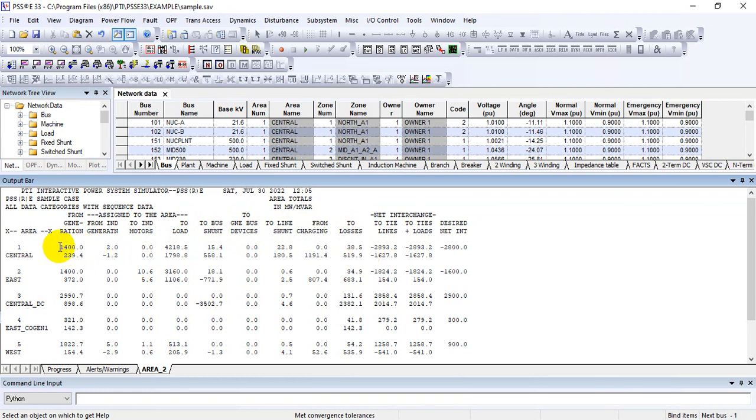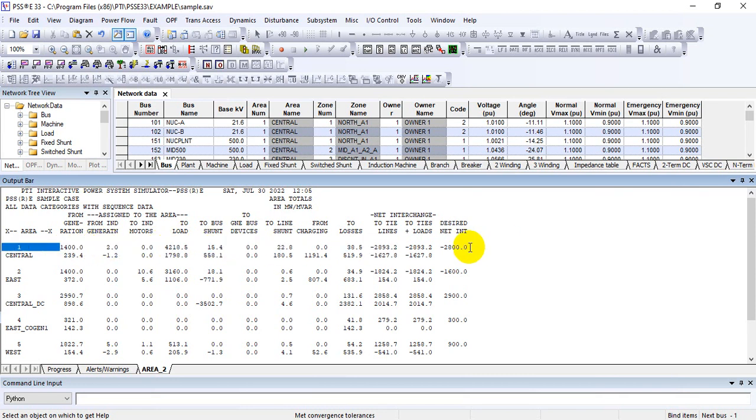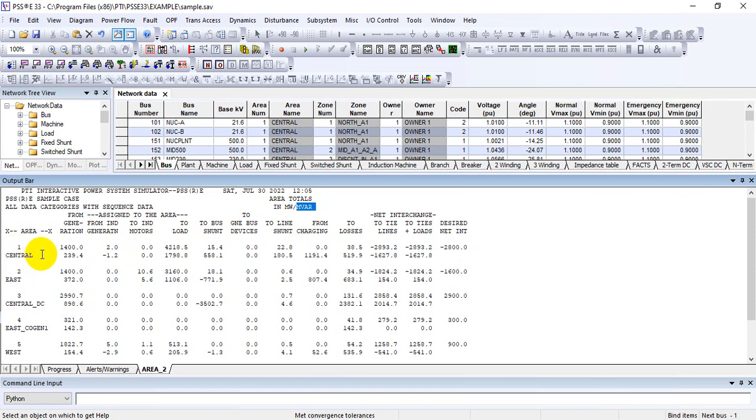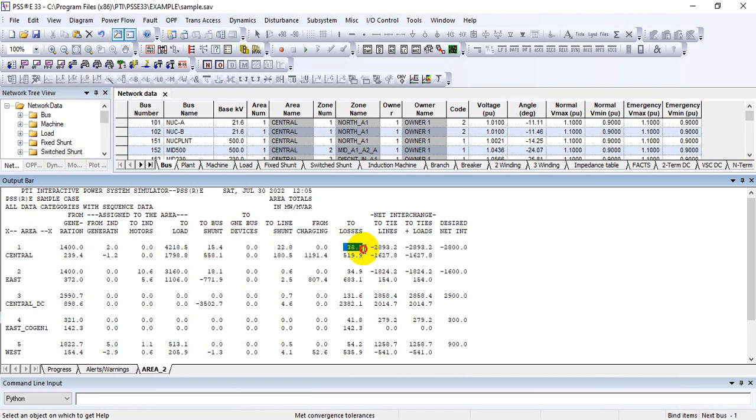Here's a very important thing to note: the first row in each column shows the megawatt. The identifiers of area total - the first upper value shows megawatt and the lower value shows megavar. For example, in Central One region, you can see that the generation is 1,400 megawatt and the reactive power here is 239.4 megavar. Similarly in each case, and also the losses in this area: 38.5, that is megawatt losses, and 519 is megavar loss.